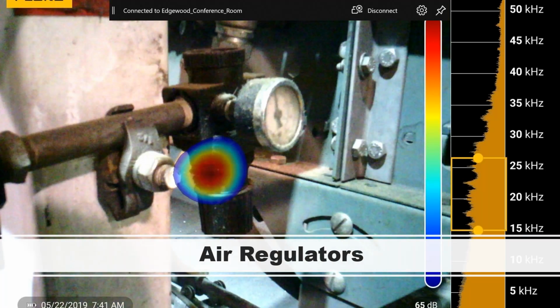Air regulators, especially when they get older, are going to start leaking. Those O-rings on that stuff are not supposed to be a consumable item, but they do wear out. Vibration, age, heat. I've found leaks on the backs where you put the gauges on because somebody didn't tape them. I've found leaks on O-rings. I found just plain old defective regulators, new out of the box. So take a look at the stuff.